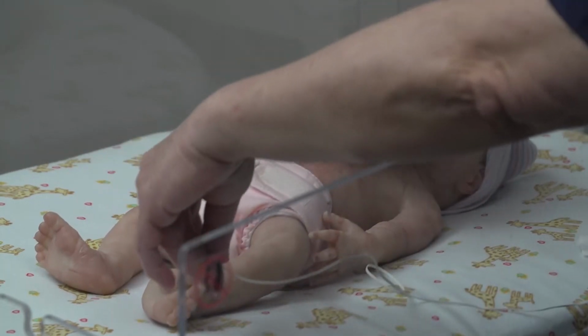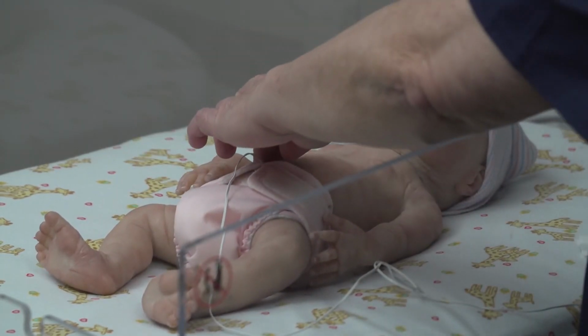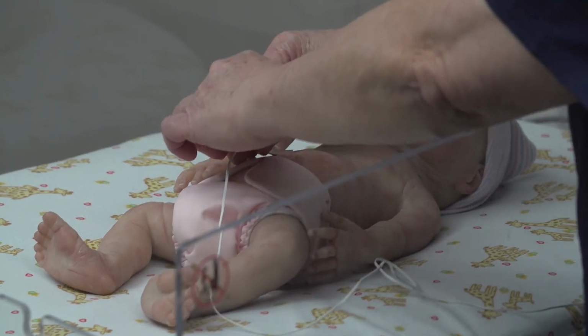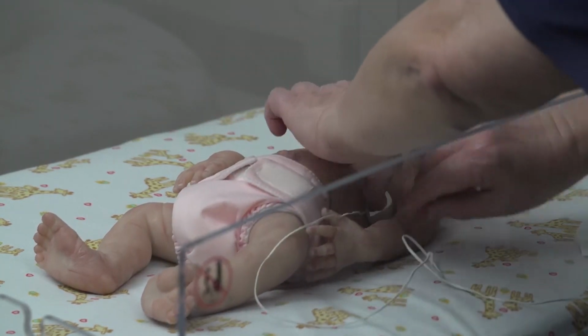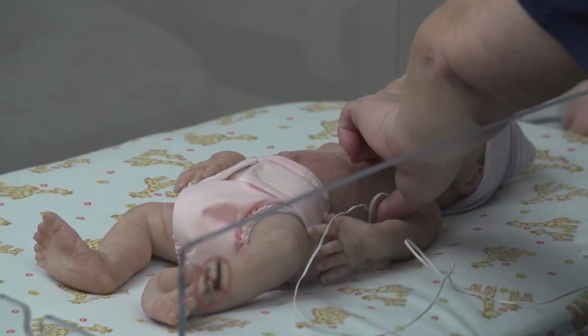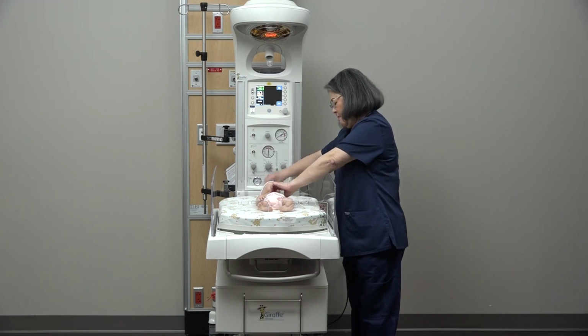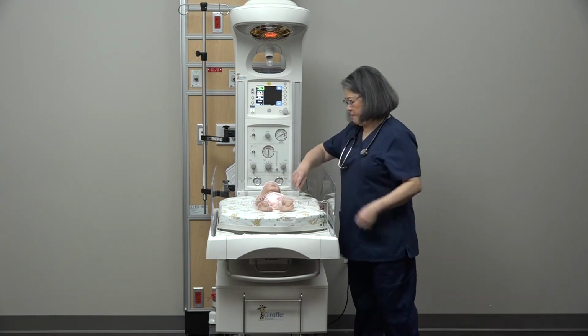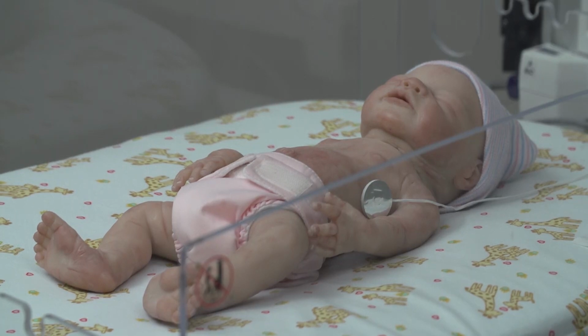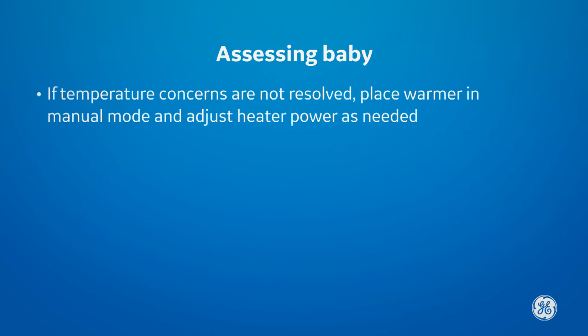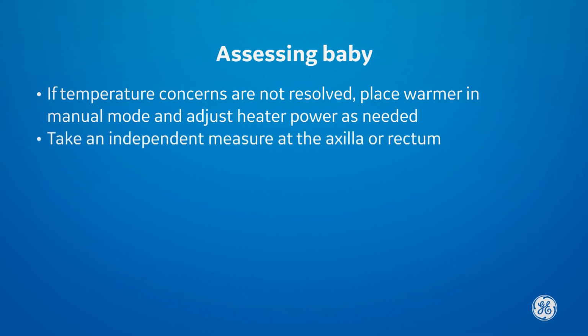If the patient shows more than a typical 0.5 degrees Celsius or 0.9 degrees Fahrenheit difference between the warmer abdominal skin temperature and a remote site, such as the axilla or rectum, consider the following actions. 1. Verify the skin temperature probe has good skin contact, using a reflective patch. Consider moving the skin temperature probe to another site, such as the axilla, and continue to monitor the patient's temperature. Adjust the baby mode set temp as needed to meet the desired temperature at the independent measurement site, such as the axilla or rectum. If temperature concerns are not resolved, place the warmer in manual mode and adjust the heater power as needed to meet the desired temperature per independent measurement, such as the axilla or rectum. However, baby mode should be used whenever possible.